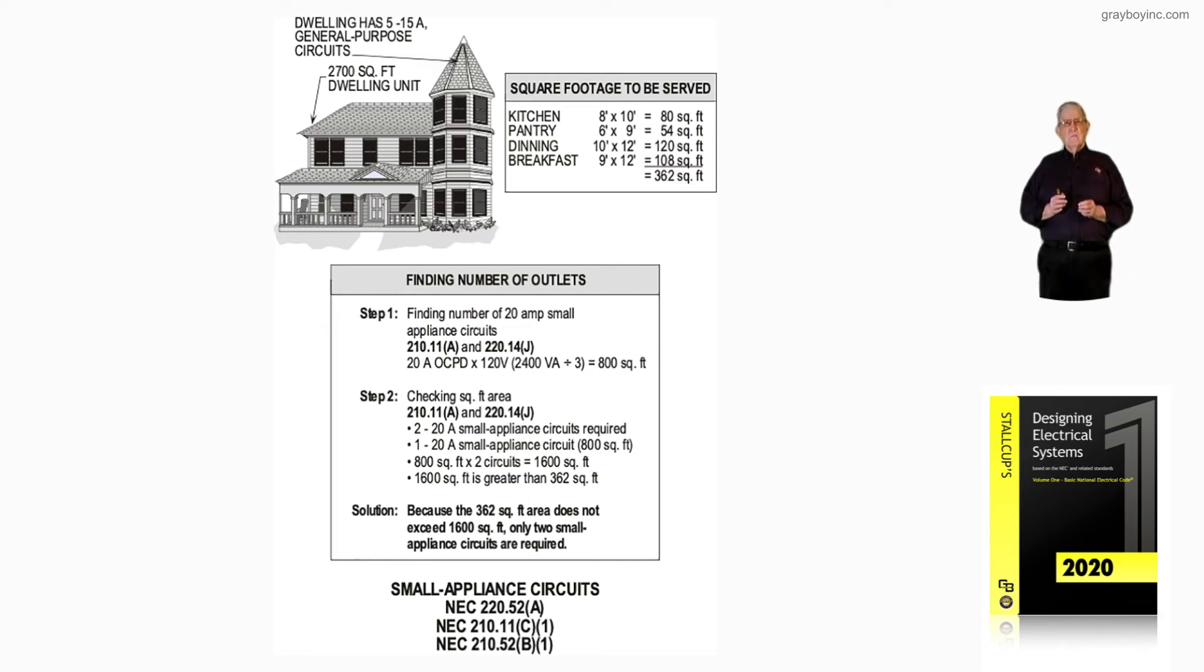basically is 2400VA, when you do your math. You divide that by the 3VA per square foot of 220.14j, you come up with 800 square foot.